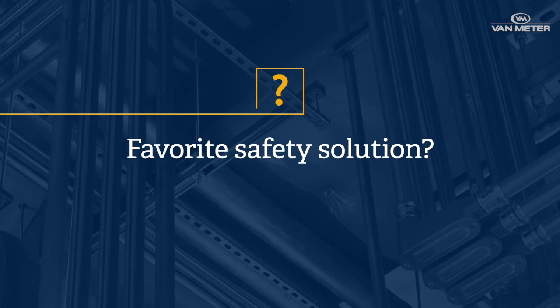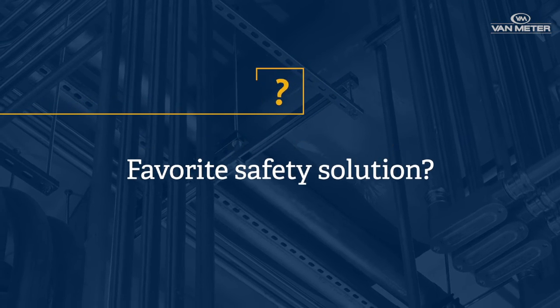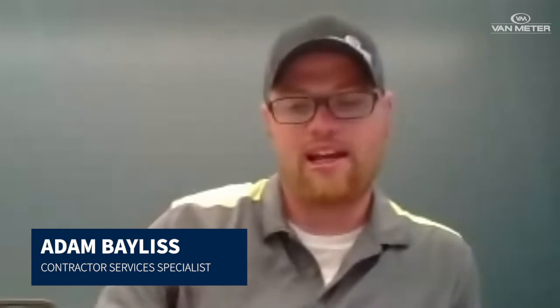I like to use Southwire's Tuggers, which are a wireless deadman switch setup, which allow the tugger to be operated and killed from both the feed end and the tugging end of a wire pull without any use of cell phone or radio.